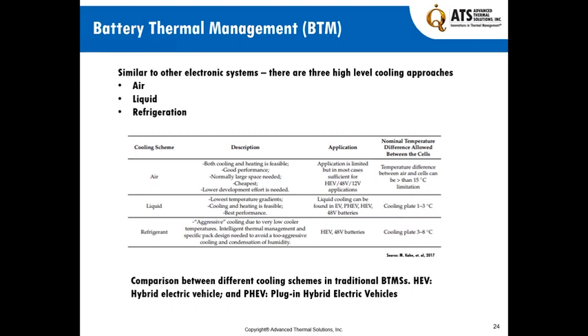Liquid cooling has the lowest temperature gradients—pay attention to this column with respect to liquid versus refrigeration. With air you see a significantly larger temperature gradient, but with liquid it's only 1 to 3 degrees C. Remember what I said earlier about the uniformity of temperature from pack to pack, or battery to battery—it's really important so we don't get the neighbor effect as severely as seen in other applications. Refrigeration is aggressive cooling due to very low cooler temperatures, requiring intelligent thermal management and a specific pack design to avoid too-aggressive cooling and condensation of humidity. Irrespective of the system type, with deployed refrigeration, condensation is a huge point of concern, and managing it could potentially be very costly.